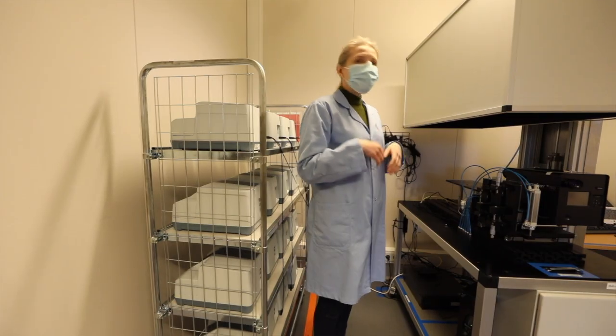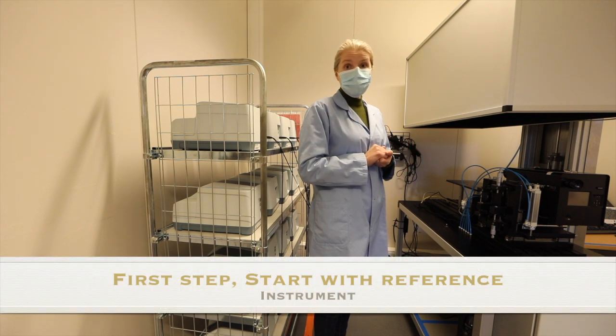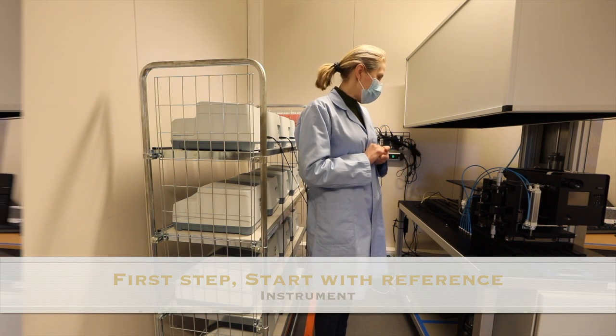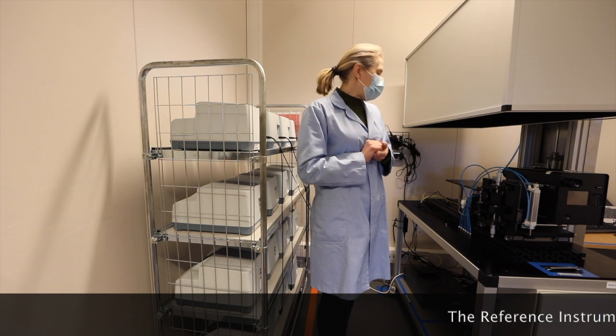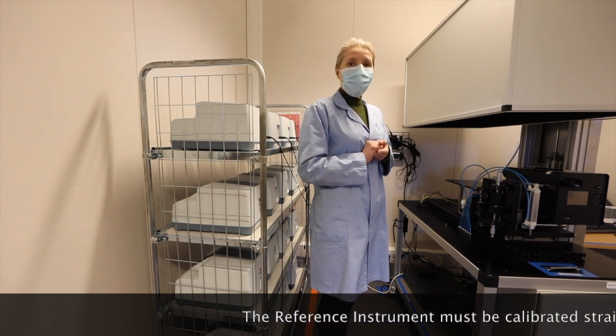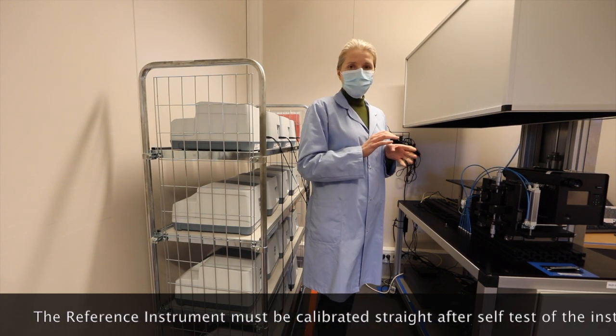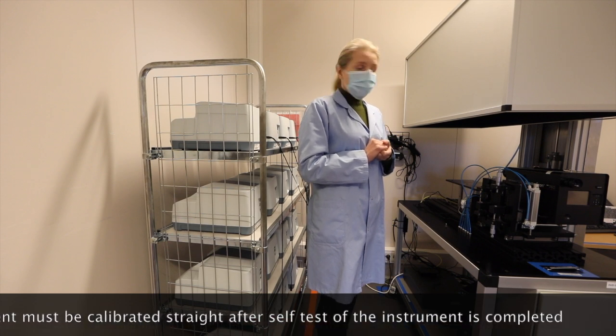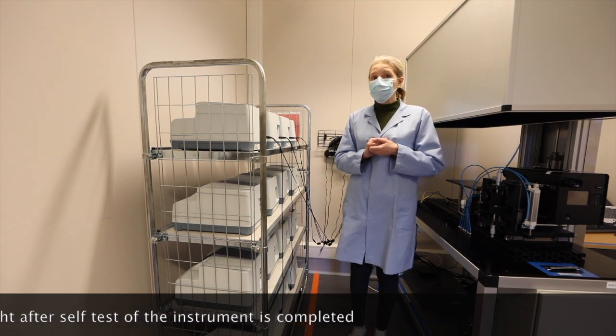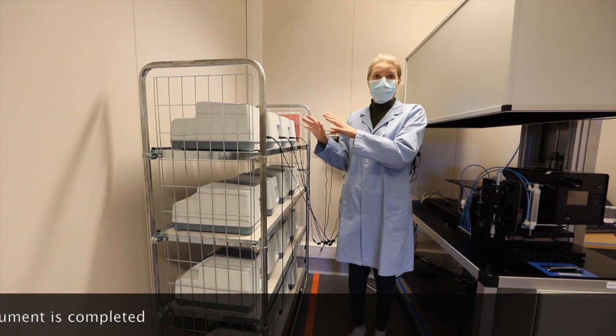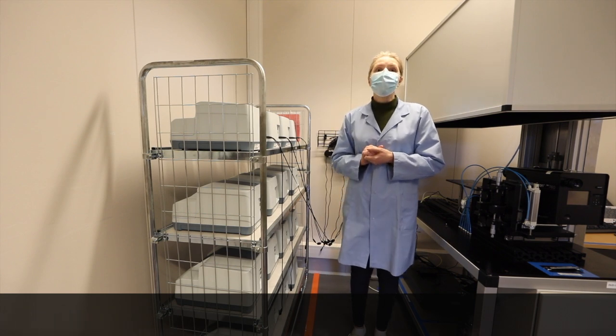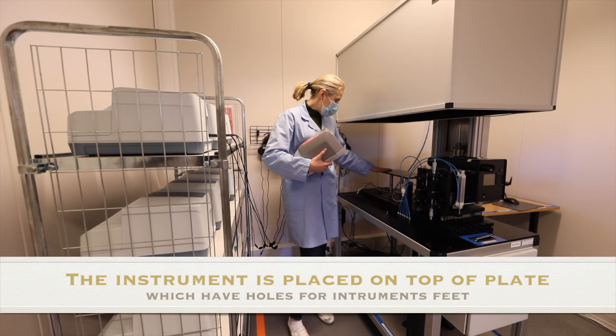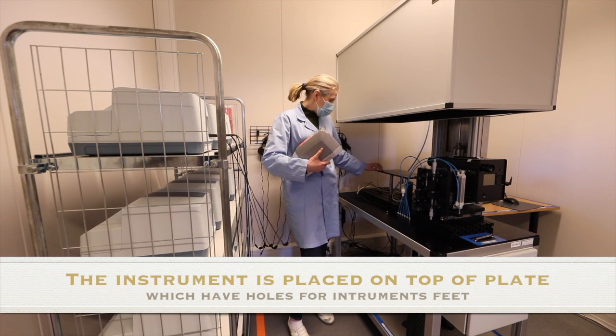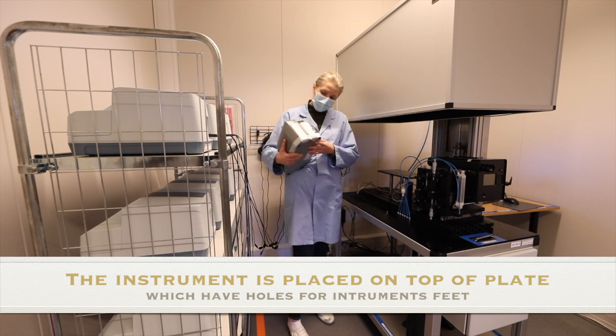We start the calibration by calibrating the reference instrument. It is important to remember that the 30-minute rule does not apply for the reference instrument. The reference instrument must be calibrated immediately after the self-test is completed. Place the reference instrument on a plate that contains holes for the instrument feet.